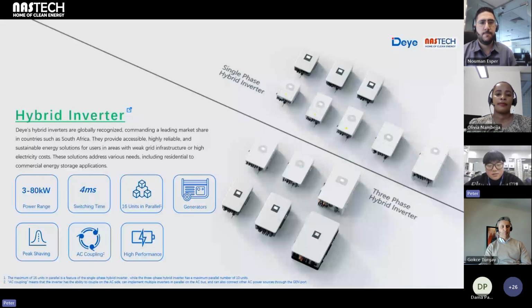And the single-phase hybrid inverter, you can parallel them in 16 units. This is also a leading number in the industry. And for three-phase, it's 10 pieces. But you can still build an 800 kilowatt system with our 80K hybrid inverter. And all of our inverters have a generator application, so you can connect generators directly to the hybrid inverter. You don't need any ATS device to do the switching from the grid.